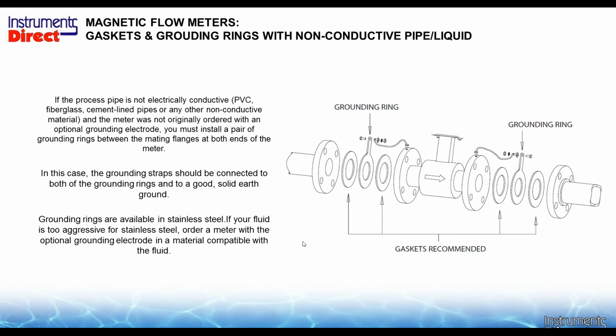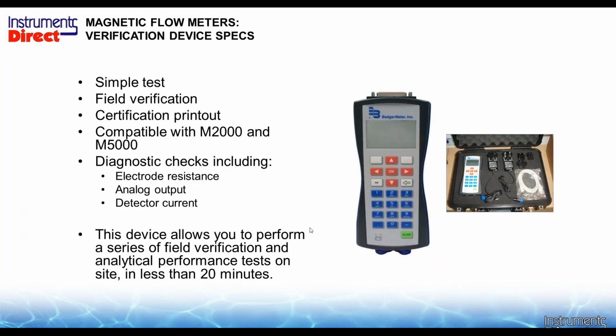Grounding ring, why use a grounding ring? A grounding ring will give you a good zero flow. That's why you use a grounding ring on a plastic-like application. And every once in a while you have an exotic application where you just have horrendous plant power, and the best thing to do then is also to ground your mag meter, and it solves a lot of problems there.